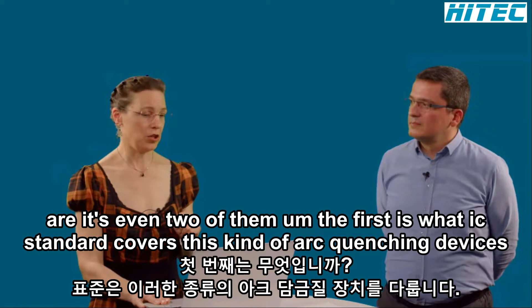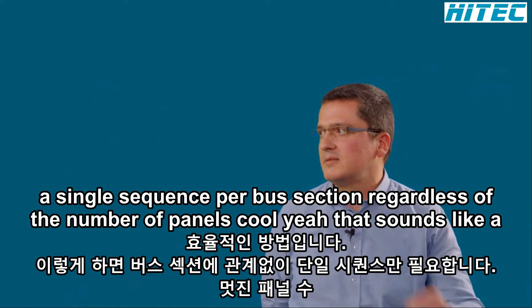The next question is: please clarify where the SIQuench is mounted - independent column, or integrated into incomer or busbar PT? As per our current offering, we mount the SIQuench as fixed in the busbar compartment. From our perspective this is the most cost-efficient way, and by doing so you require only a single SIQuench per bus section, regardless of the number of panels. That sounds like a plausible solution.